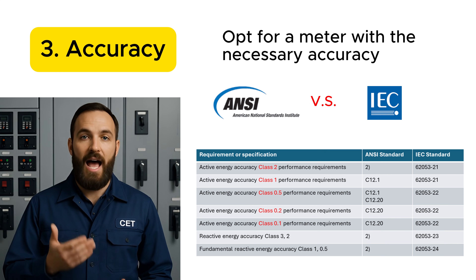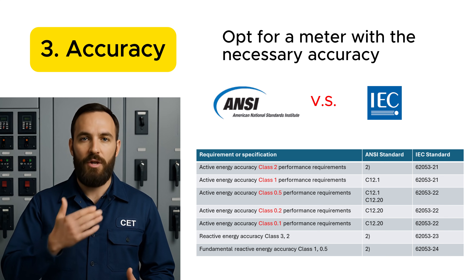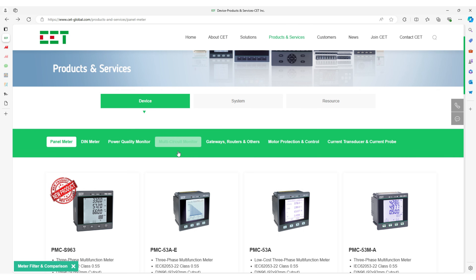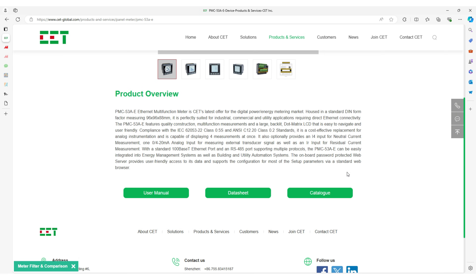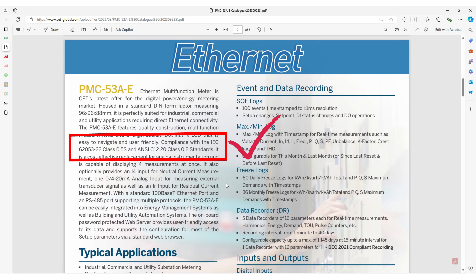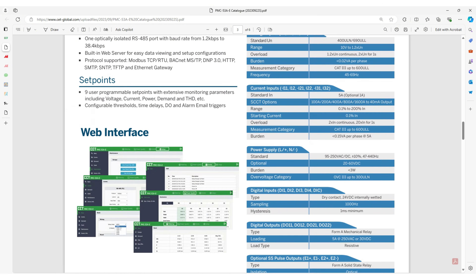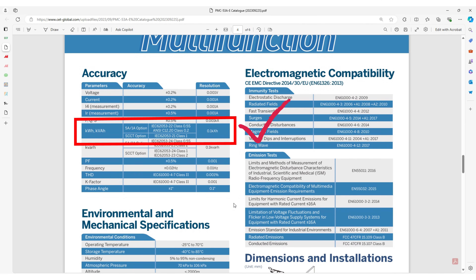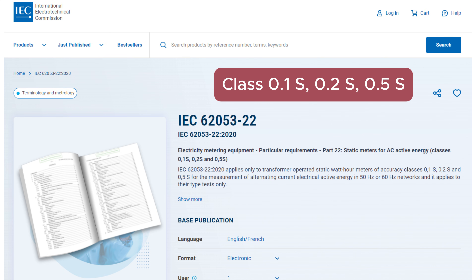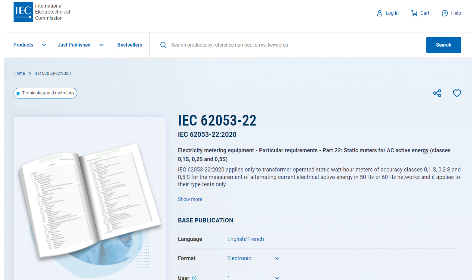Number 3: Accuracy. Opt for a meter with the necessary accuracy. ANSI C12.20 defines the accuracy requirements for revenue-grade meters with accuracy classes of 0.1, 0.2, and 0.5. These classes indicate the percentage error allowed in the meter's readings. Similarly, IEC 62053-22 specifies the requirements for static meters for active energy, for example class 0.5S and above, ensuring high accuracy in energy measurement.